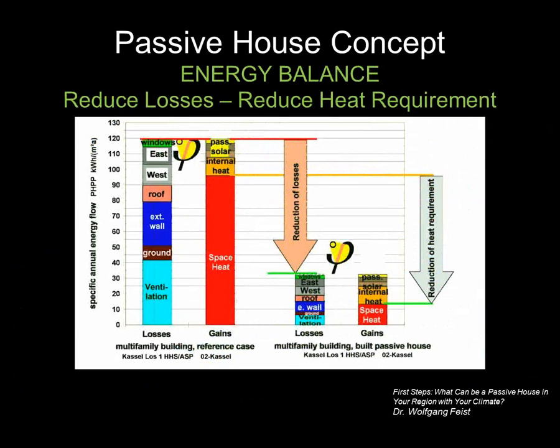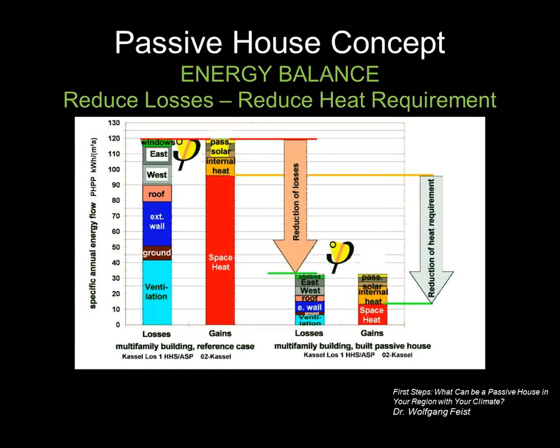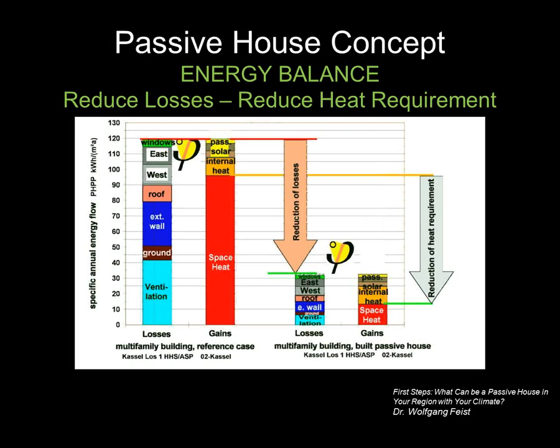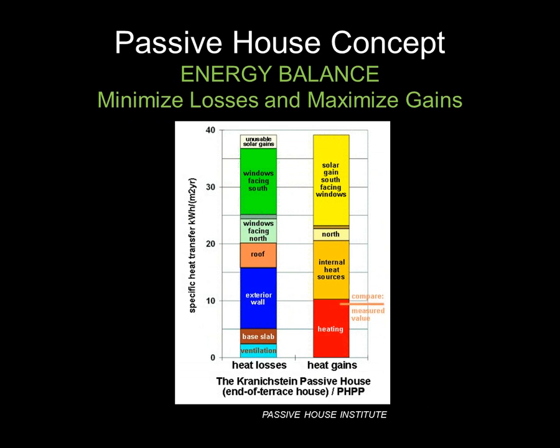As I said before, Passive House really is relying on a reduction of loads within the building to then be met through passive means. This chart here shows a conventional building versus a Passive House building, and it shows how through the dramatic reduction of losses, one then only has to supply a limited amount of gains to meet the need of the building. And the idea that this represents a balanced energy load through minimizing losses and maximizing gains is really central to the Passive House idea.